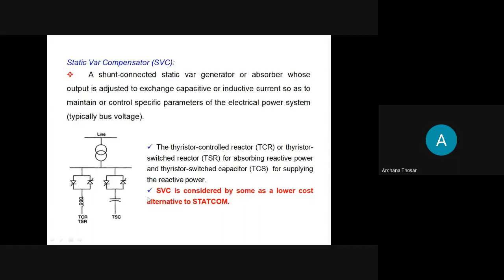Now there are some good articles wherein SVC, the static var compensators, and the STATCOMs are compared, wherein the STATCOMs seem to be better in terms of the control system, because you can get transient-free operation. There are various parameters on which you can compare them, but harmonic generation is very less in terms of STATCOM. It is only high in terms of a fixed capacitor, because the fixed capacitor will not help us to reduce the harmonic levels.